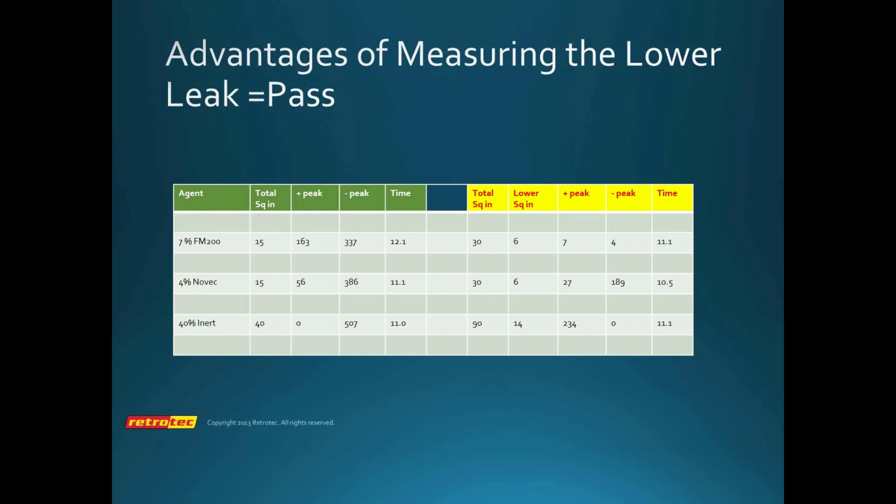Now that doesn't mean that we're never going to install PRVs in the US. There are often situations where we must install PRVs, but this would be one way where, in measuring the enclosure, we can either tell what the PRV size should be more accurately, or do less air sealing in the room, which can save a huge amount of money, or, as I mentioned earlier, have a situation where the same enclosure can pass the retention time or hold time requirement and the peak pressure requirement without a PRV.